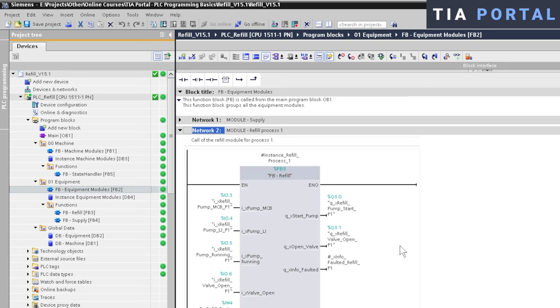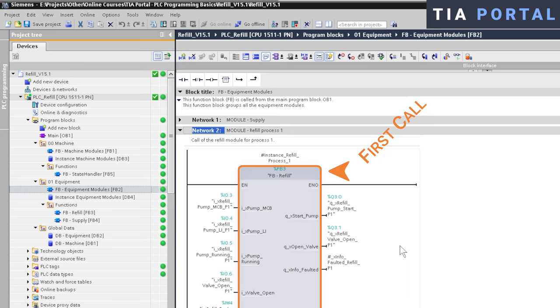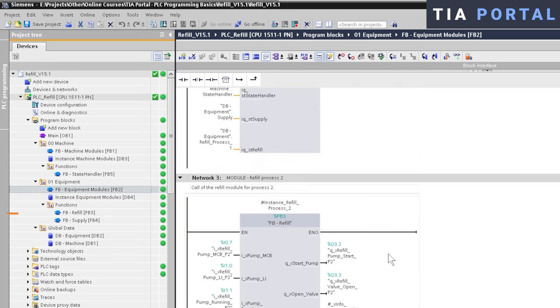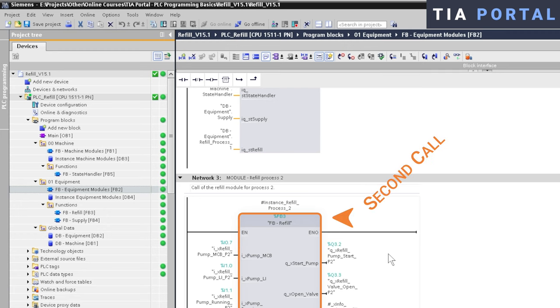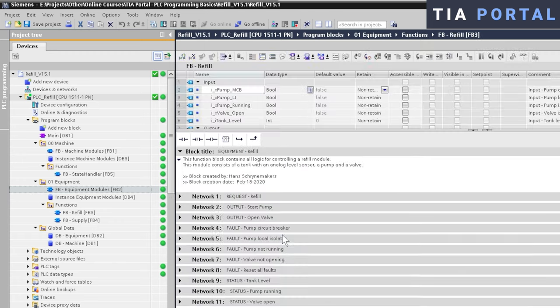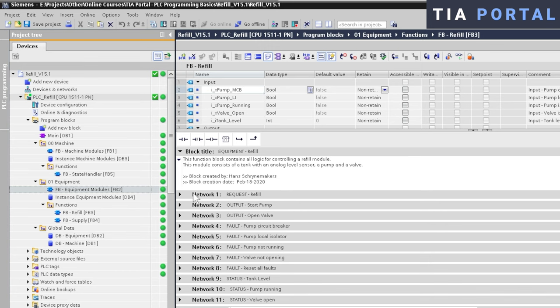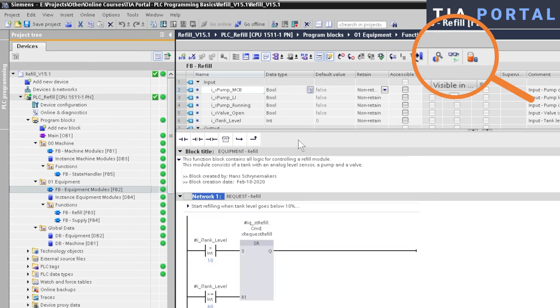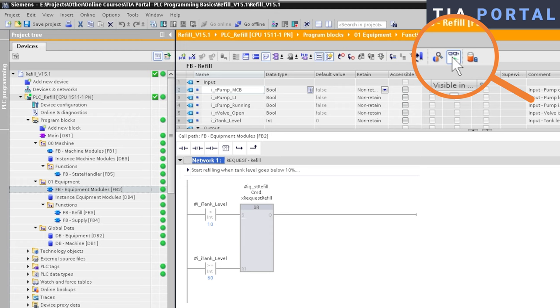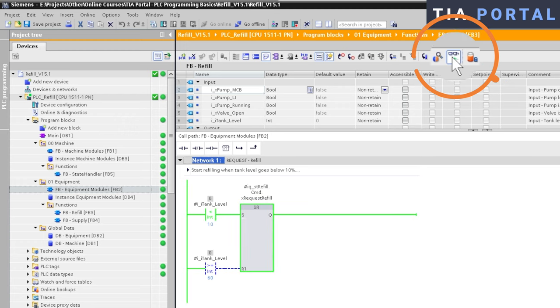But what if you have a reusable function block that you call multiple times in your user program? Here on our sample application, we have the function block FB Refill, which is being called two times. Let's assume that there is a problem with Refill Process 1, for example the process should have been started, and we want to monitor inside the function block to find out what is going on. So we open the function block and we go online. There we go. The green colors in the ladder logic are now indicating that we are monitoring the logic.